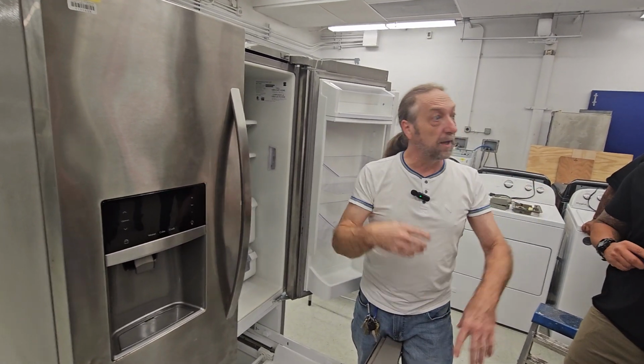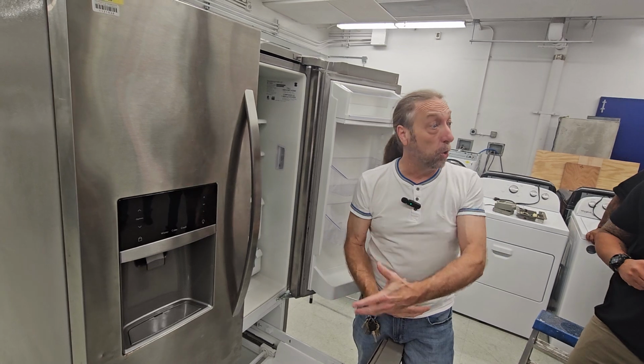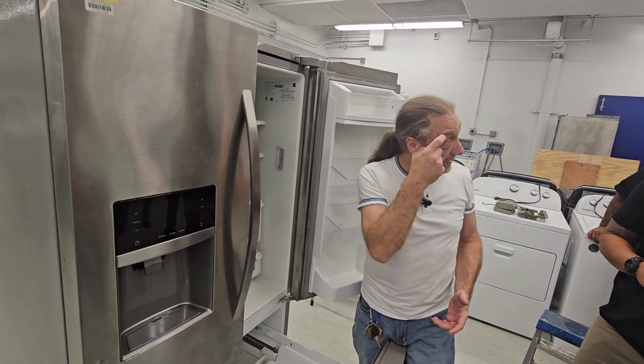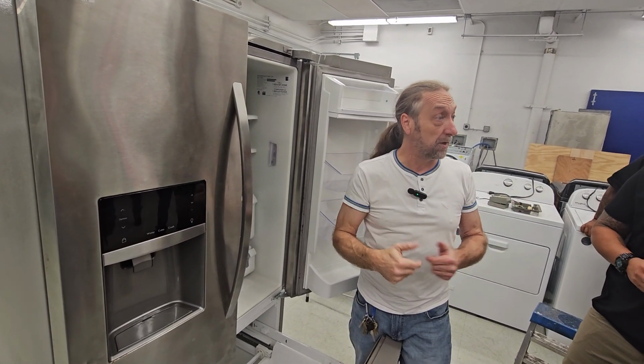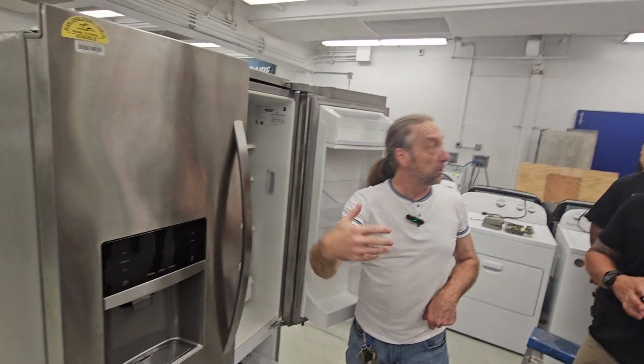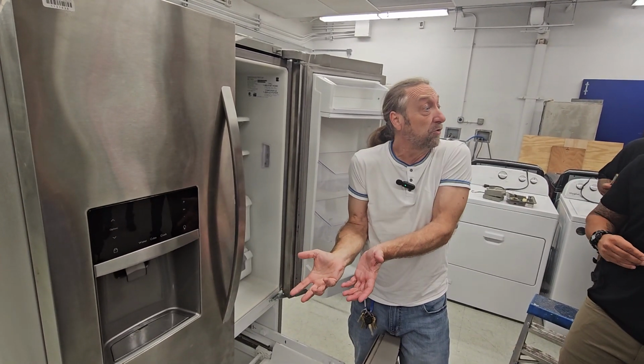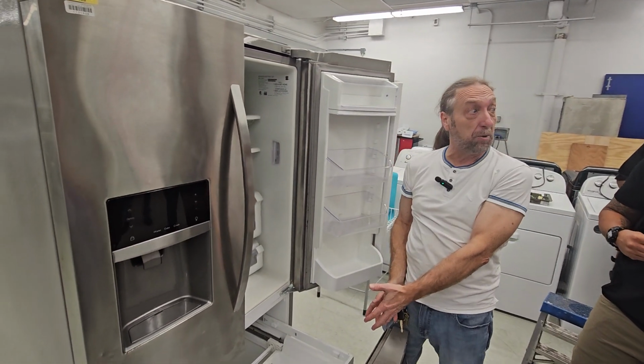One of them is good and the other one is shorted or open. You have to look at the diagnostics to see what that is. I'm not going to tell you guys what it is, you have to figure it out. But when you go through diagnostics, it checks the sensors for you, so you don't have to tear the whole machine apart just to check the sensor.